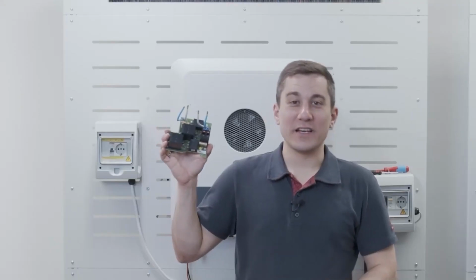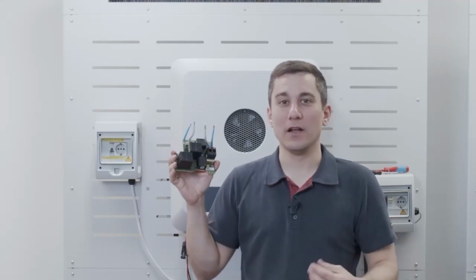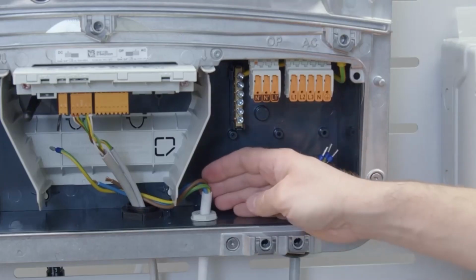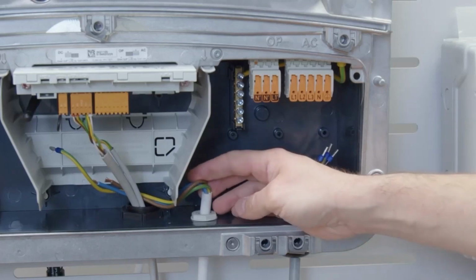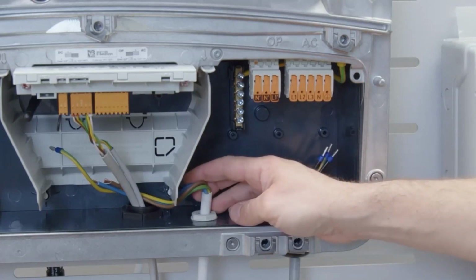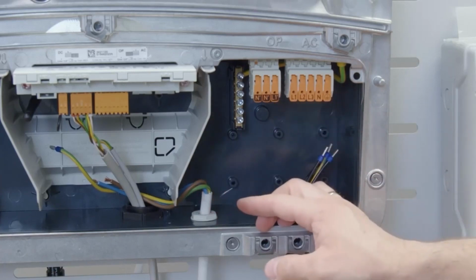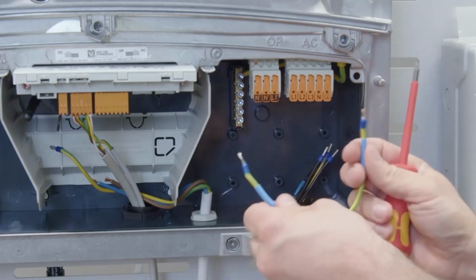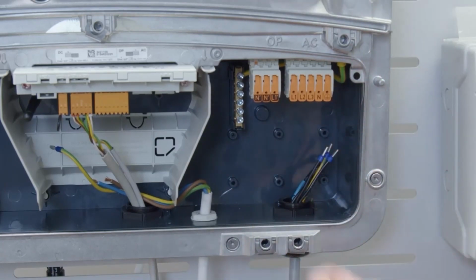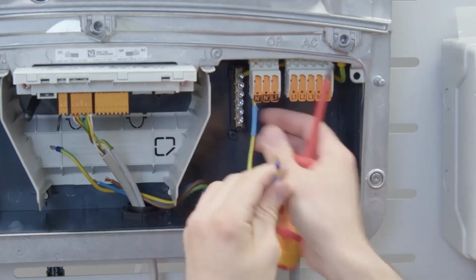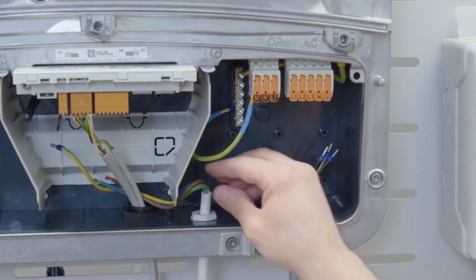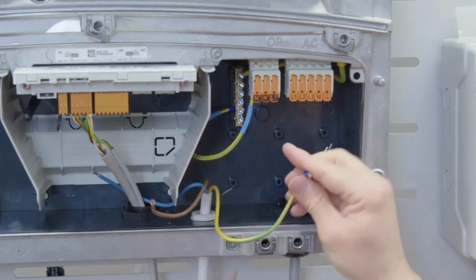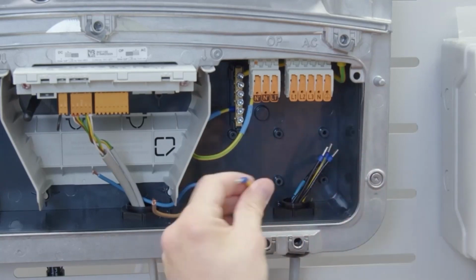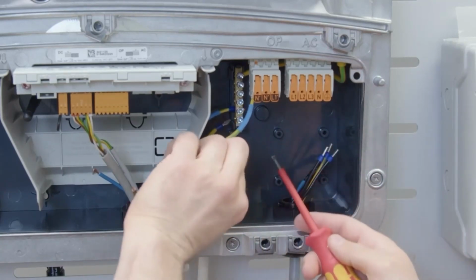With the PV point comfort, a continuous supply of your emergency power loads is possible. When the PG clamp is installed on the inverter space, we next can install the AC cable coming from the emergency power device and install it to the PV point connection of the Gen24 Plus. To do that, we start with the protective earth cable, and we now need to make sure to get the protective earth signal from the PV point clamp to the PE clamp of the inverter. Second thing, we want to install the PE cable coming from the emergency power device directly on the PE clamp in the inverter.